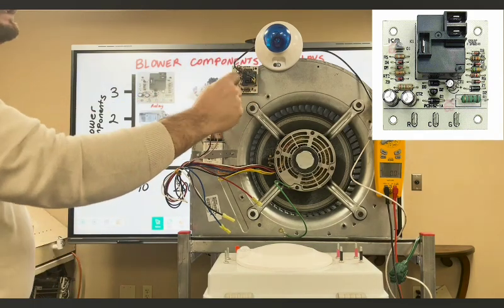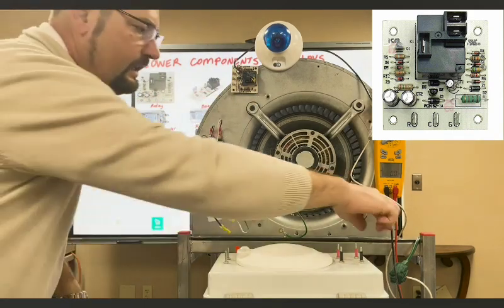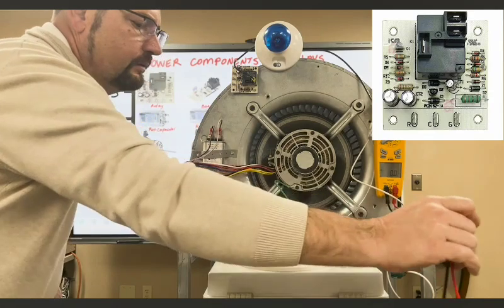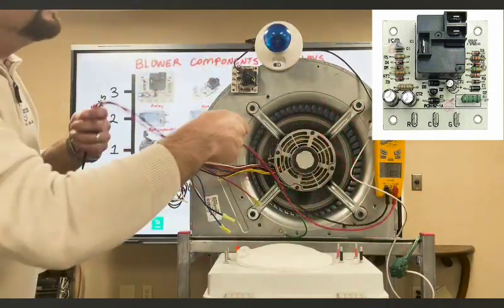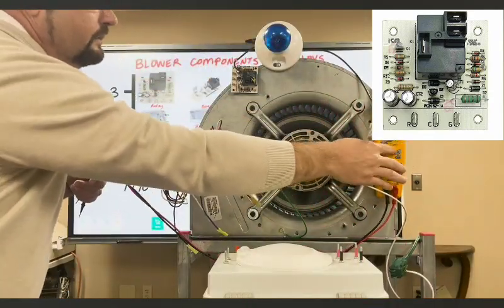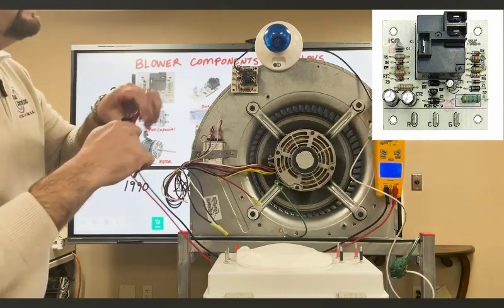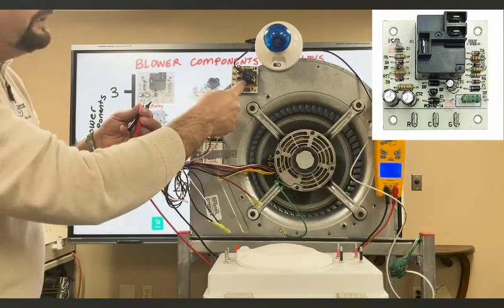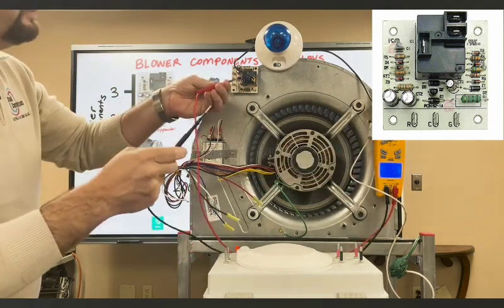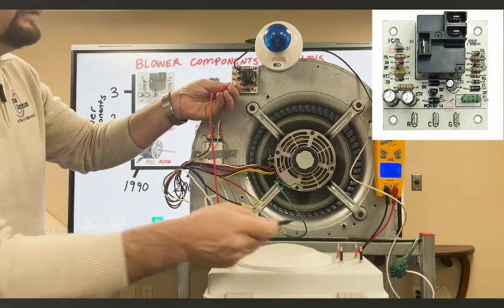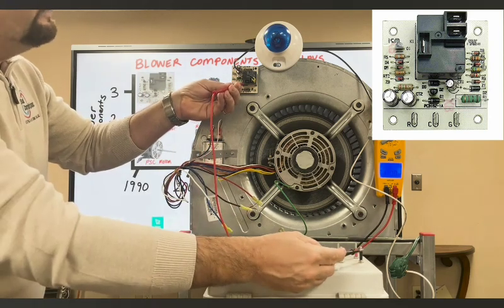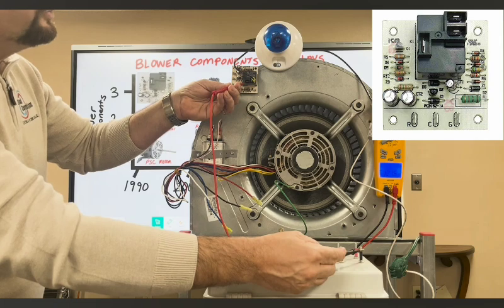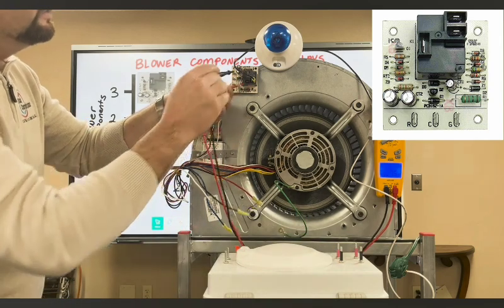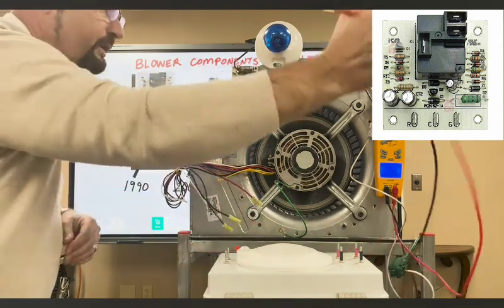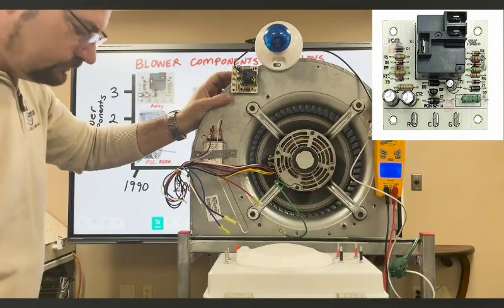Now this is normally closed, so to test that path, I'm going to take my meter. In theory, if I'm normally closed between here and common, then I should be able to read neutral over here. I'm going to test to one of my line voltages and see, therefore I have 120 volts sitting here. All right, so I have a good path, so I have a good connection.